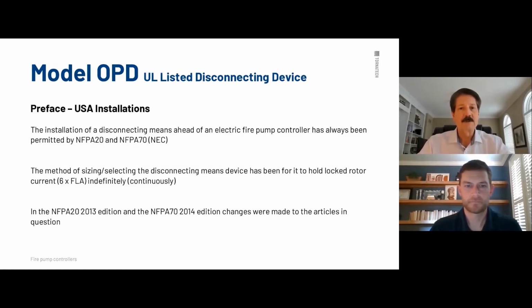The method of sizing is very simple. Typically, the disconnecting means must be able to hold lock rotor current indefinitely, 6 times full load amperage. Again, most people have used fuses in the past, and that could be confusing sometimes because there are times where electricians aren't really totally familiar with the ruling and the law saying you must go 6 times full load amperage, because what you don't want is this to open up before the fire pump locked rotor situation trips offline.